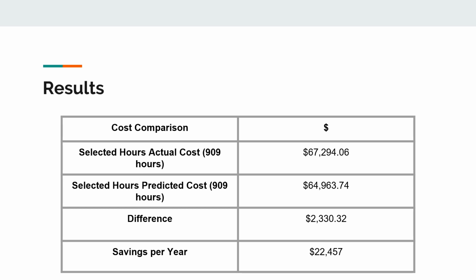Lastly is a cost comparison between how much the university actually spent on the chilled water system versus what would have been spent if our algorithm had been employed. The time frame of interest is about 900 hours between February 12, 2019 and February 12, 2020. As can be seen, the algorithm would have potentially saved over $2,300 during this time span. This correlates to annual savings for the university of nearly $22,500.